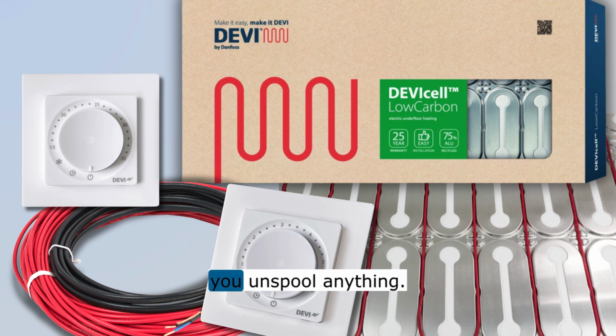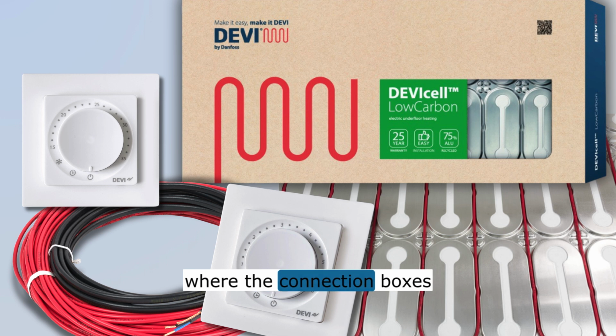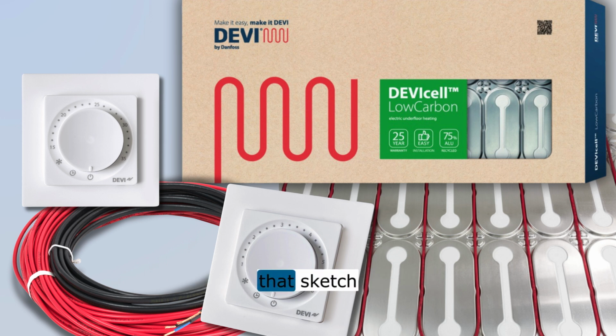It begins before you unspool anything. The foundation must be surgically clean. Any sharp object, an errant nail, or even a jagged stone can nick the cable jacket and compromise the insulation. The manual also heavily insists on drawing a physical sketch. You have to map exactly where the cold leads are, where the sensors are placed, where the connection boxes are, and you have to leave that sketch in the fuse box. Because, as we discussed, once the concrete is poured, you are flying blind. You need a treasure map if you ever need to troubleshoot a sensor.